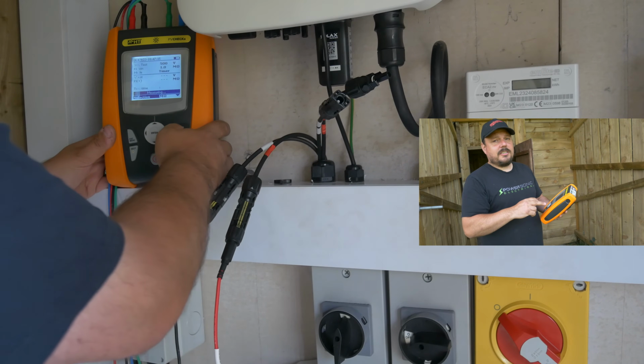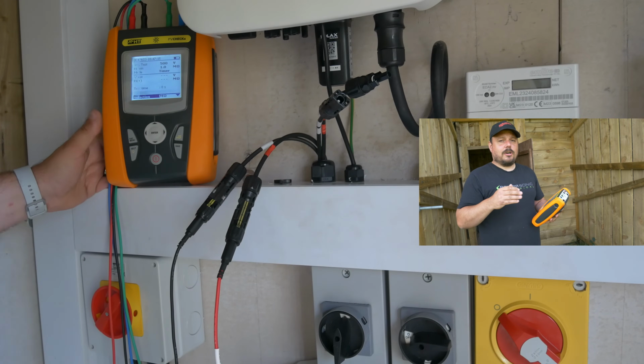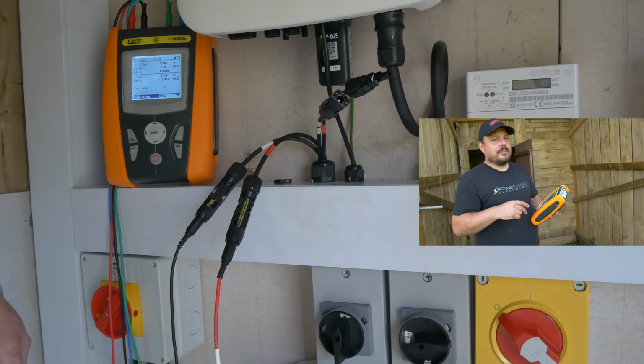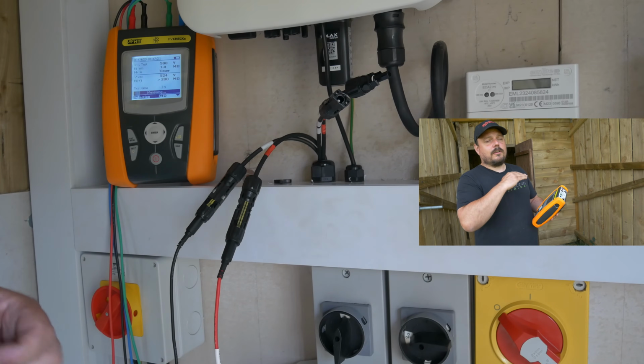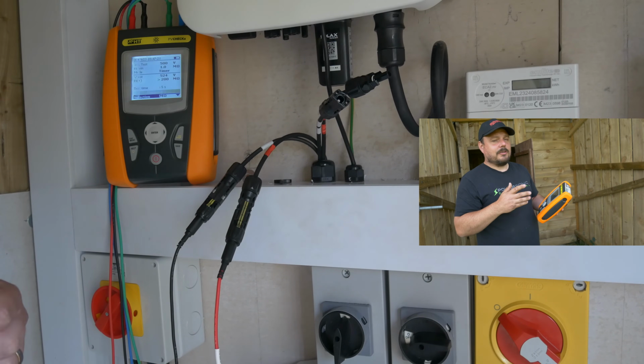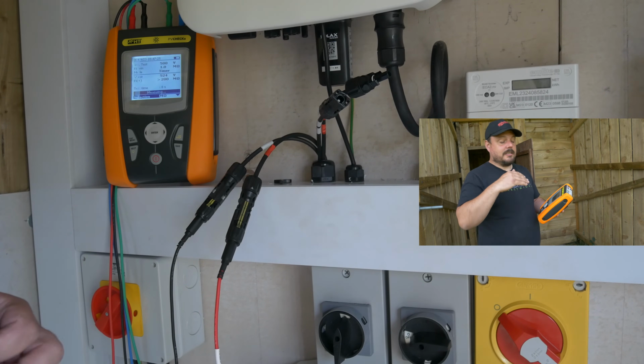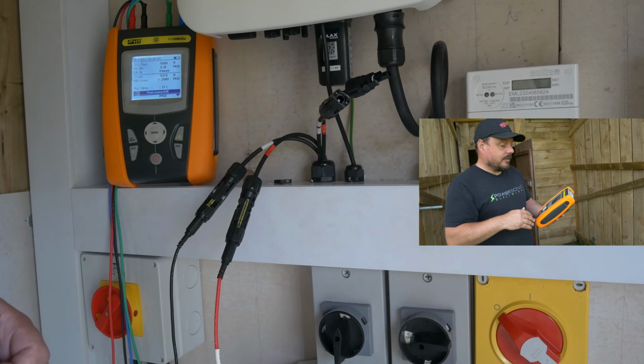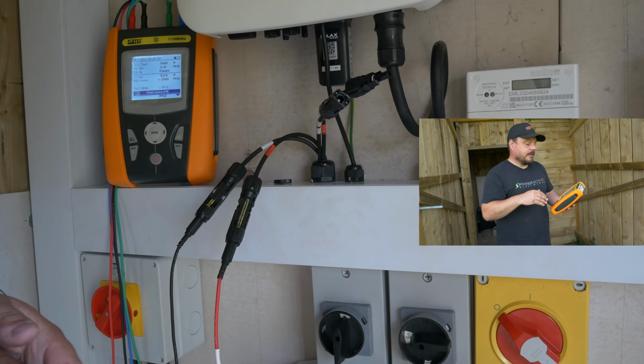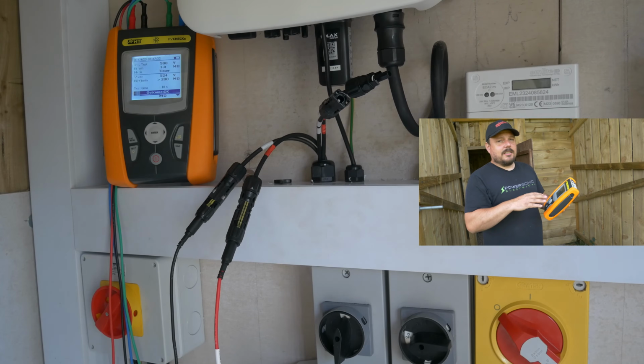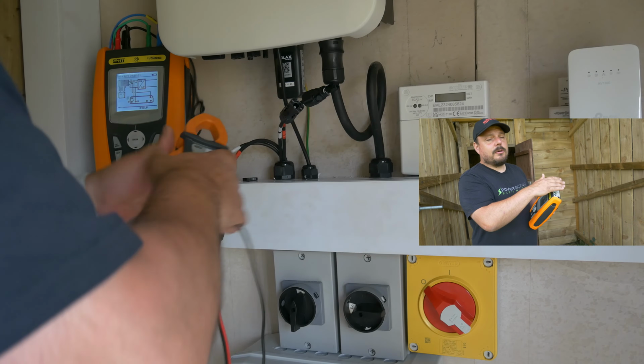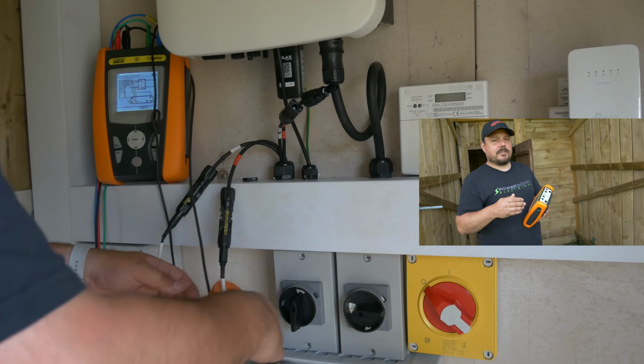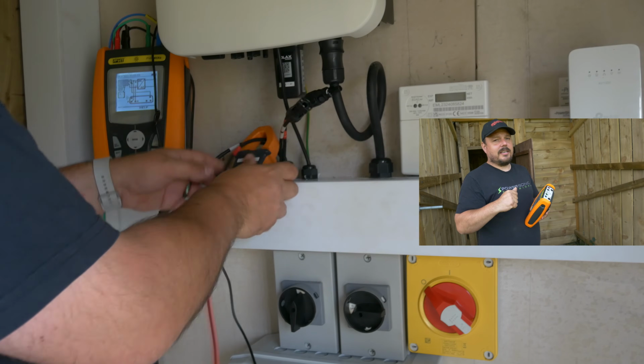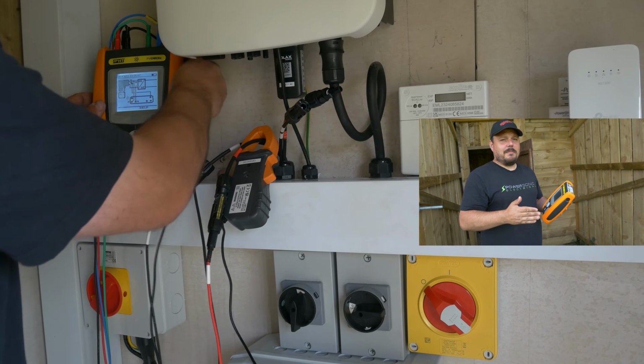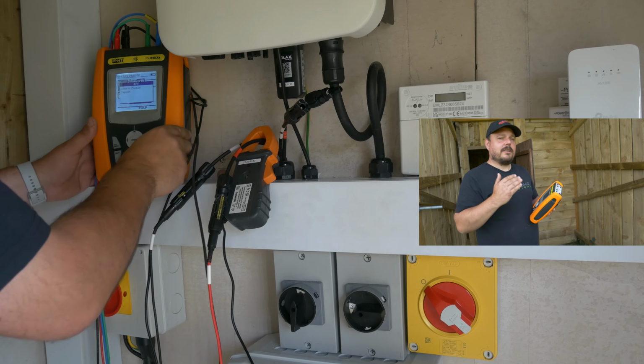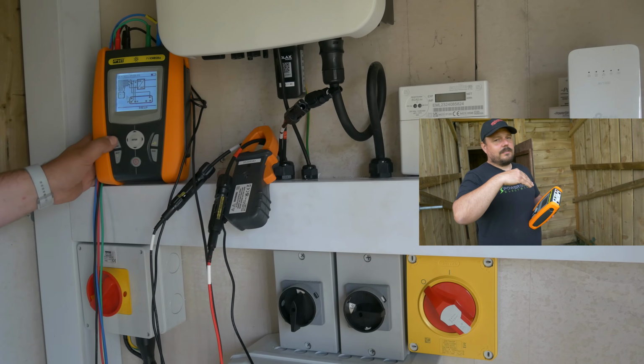And it will do an efficiency test, so it will tell you how your panels are performing, alongside a product I'll show you in a minute that we use to put on the roof alongside the array, so we can see how the system's performing based on the sun that's hitting onto it. And you can also do adjustment of the settings within this. So if there is a remote probe for the irradiance meter essentially, so the system I've got uses a hardwired lead, and you're kind of limited to about 3 meters away from the instrument up to the array, which obviously if you're out on the roof isn't practical.